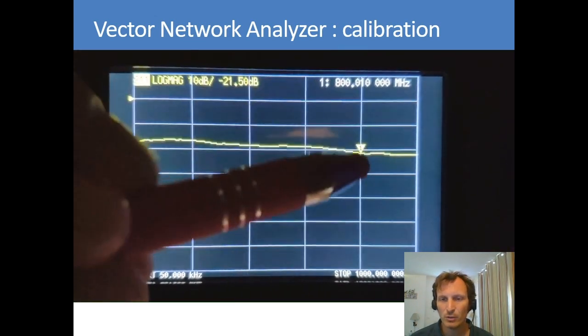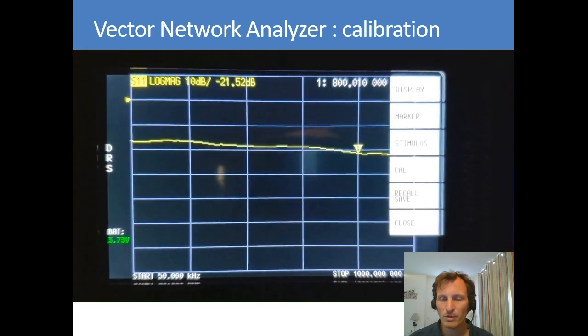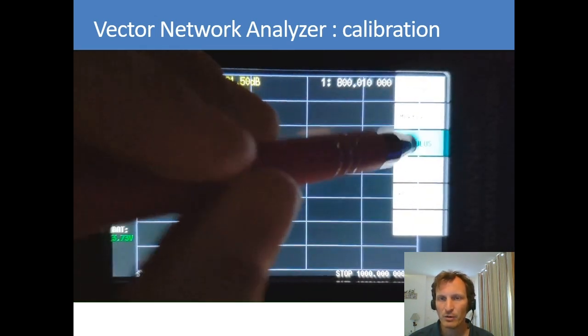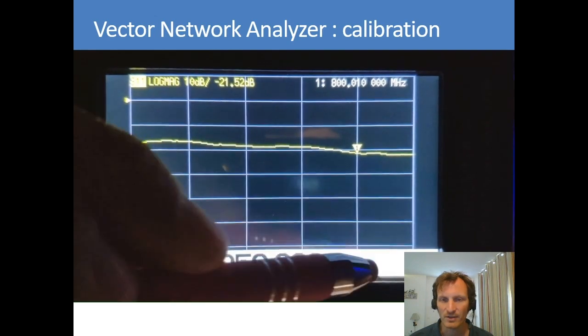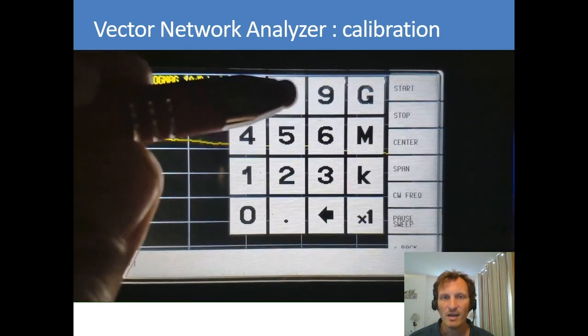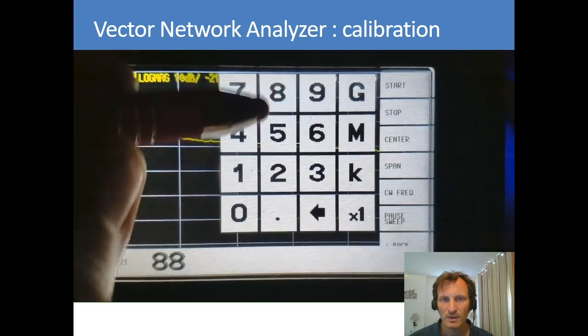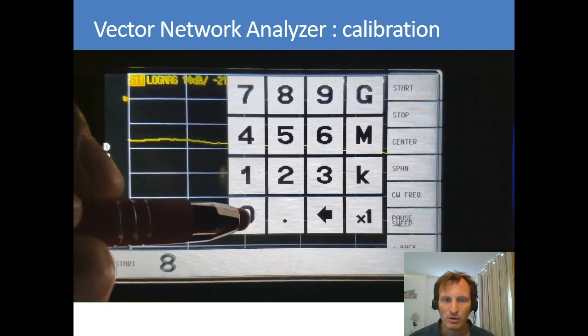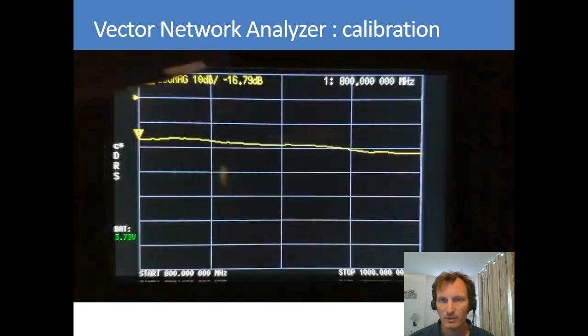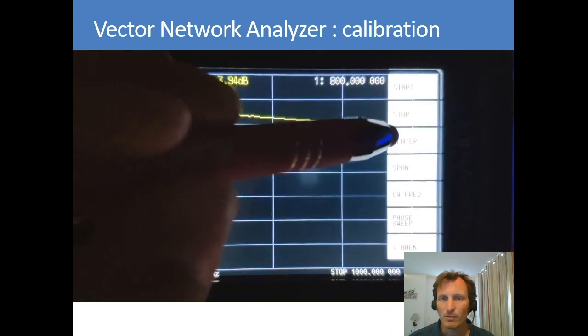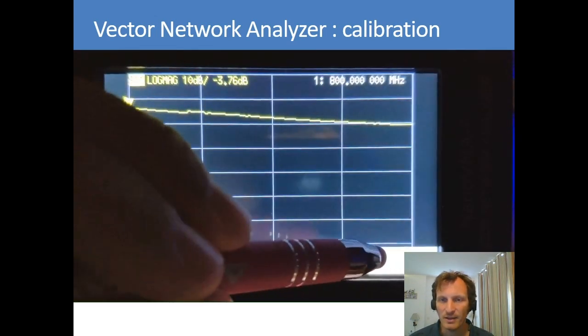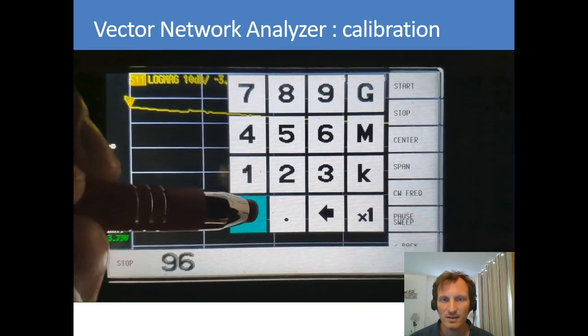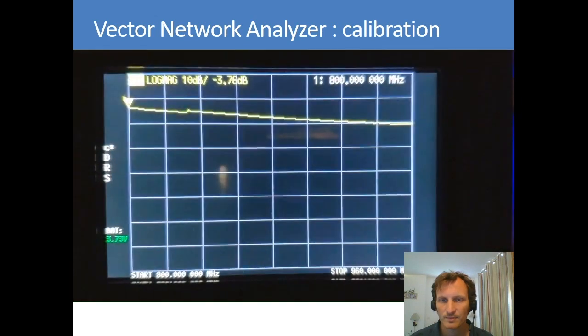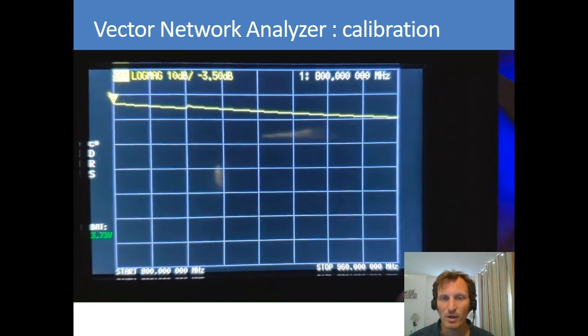The first thing that you need to do before starting the measurement is to choose the frequency band you are going to measure. First you click on stimulus, and then you choose the lower frequency, so click on start, and here we are going to select 800 megahertz. You can see that the touchscreen is quite good, but use a pen, it's easier. Then we are going to define the maximal frequency. So you click on stop, and here we are going to choose 960 megahertz. Okay, and then we can start the calibration.